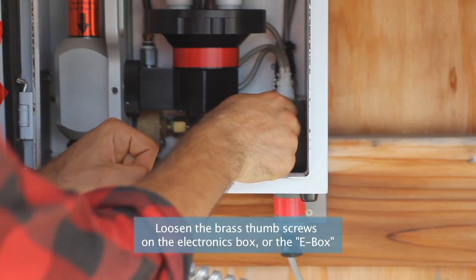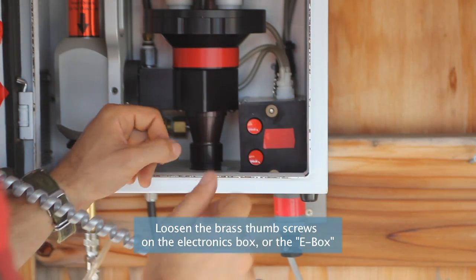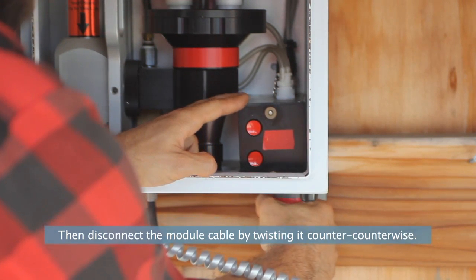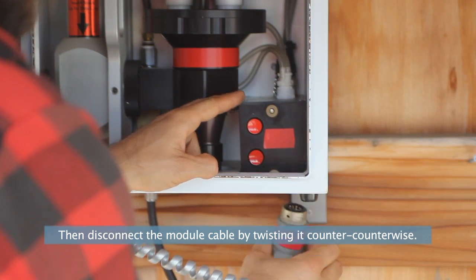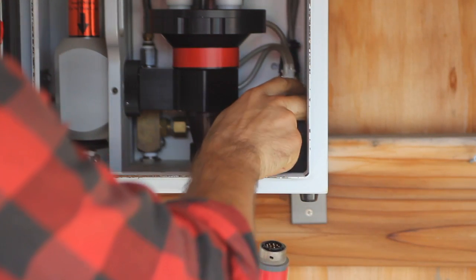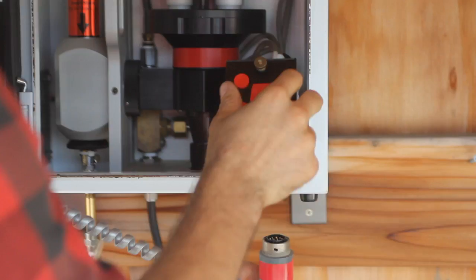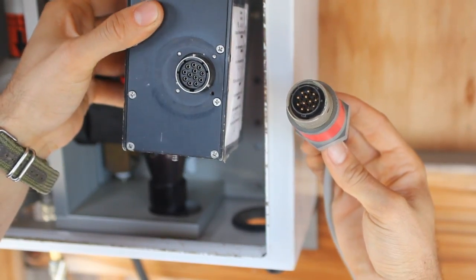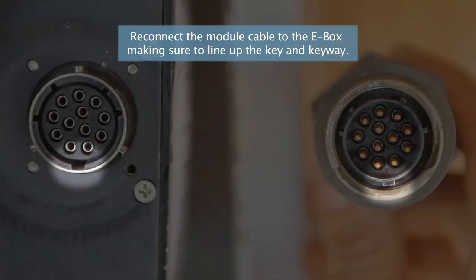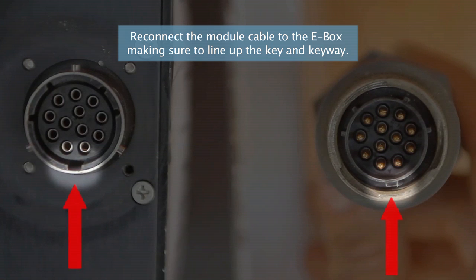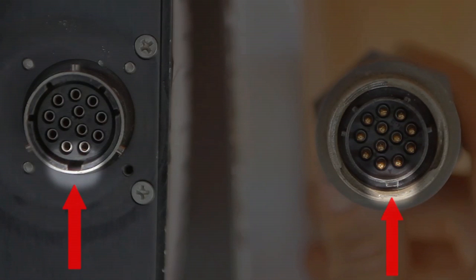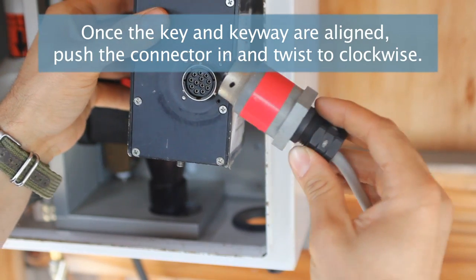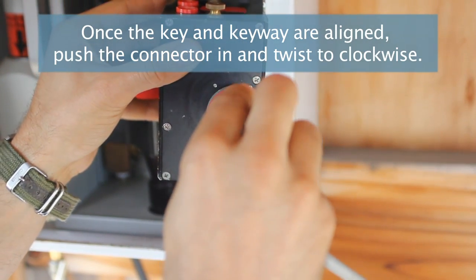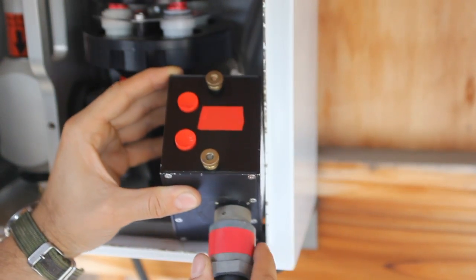Loosen the brass thumb screws on the electronics box, or the E-box. Then disconnect the module cable by twisting it counterclockwise. Reconnect the module cable to the E-box, making sure to line up the key and keyway. Once the key and keyway are aligned, push the connector in and twist clockwise.